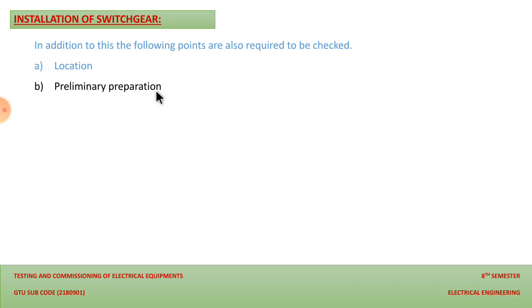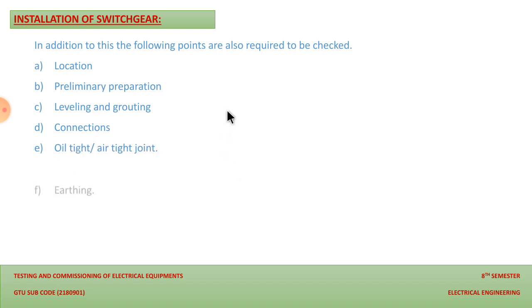Then next is the preliminary preparation that we should do for the installation of the switchgear. The third is leveling and grouting, which is again necessary for proper installation. Then the connections that we are going to make for the circuit breaker or switchgear for operation, we need to check. Then the oil-tight and air-tight joints we have to check for leakage. Then earthing, which we need to check for protection. And the drying of the insulation: if there is moisture inside the operating mechanism, we should perform a drying-out test before we connect our switchgear with the main system.